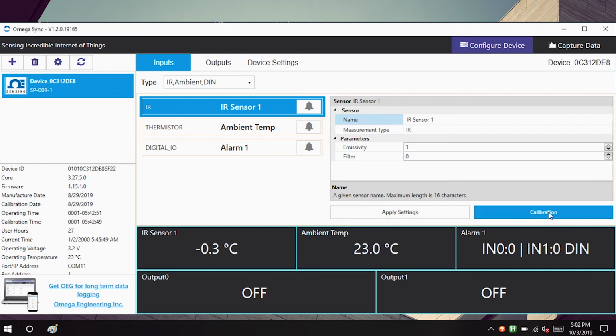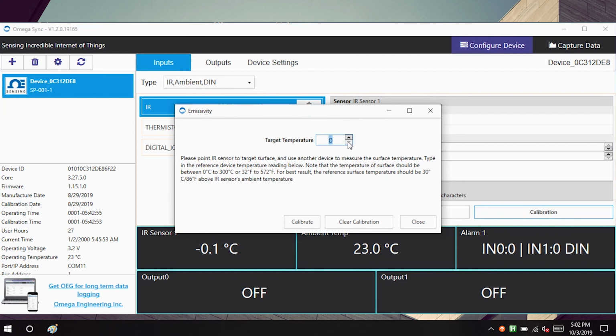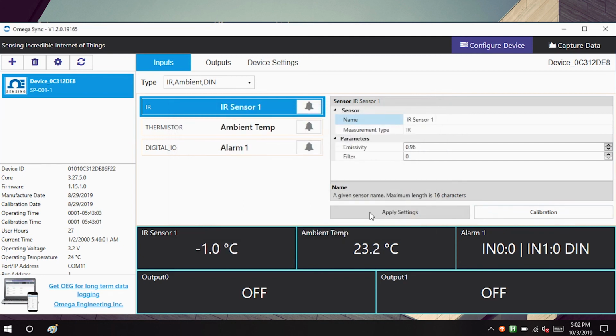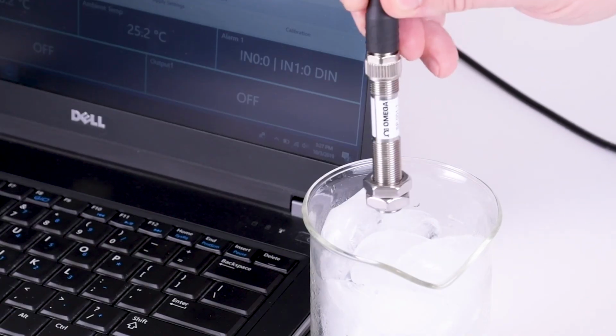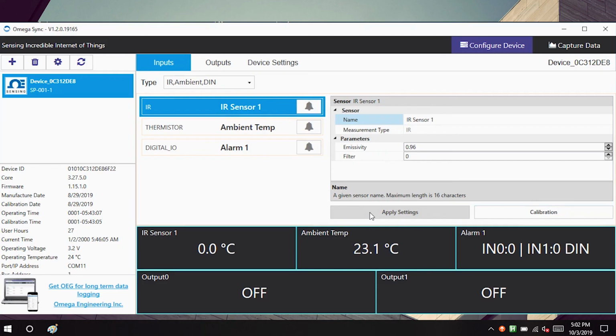Well, you can click the Calibration button and enter the target temperature of 0 degrees Celsius. Click Calibrate and then click Apply Settings to finalize. And now we'll point the smart sensor at the ice, and we're getting 0 degrees.